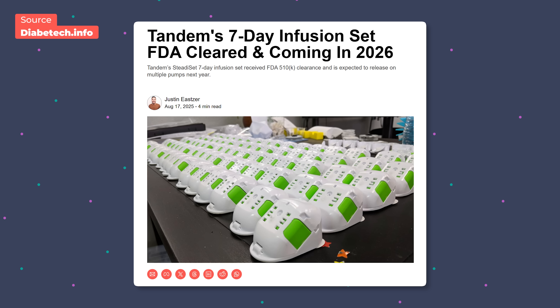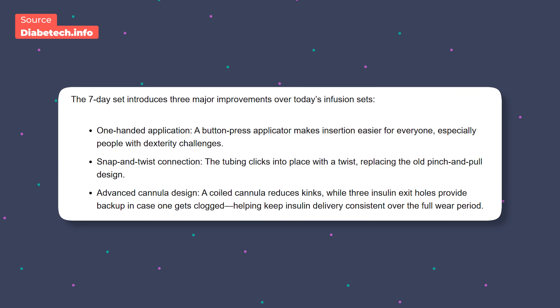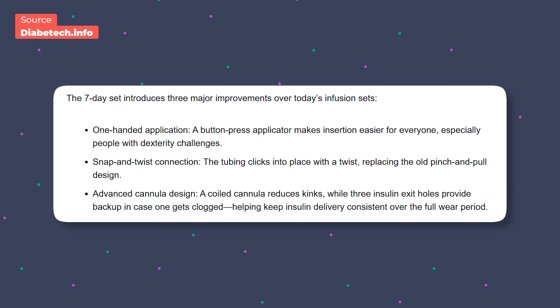Now here's where things get interesting. Tandem's SteadiSet infusion set, which is an extended wear of seven days, was just cleared by the FDA. This SteadiSet has a few advancements over current sets. First, you can easily put it on with one hand, which is better for dexterity — you just push these buttons and it will apply it, very similar to current CGM applicators. This will be great for people who have problems with dexterity, maybe they only have one hand. The new tubing will also be easier to latch on to the infusion set — it will be more of a twist and snap rather than a pinch and remove.